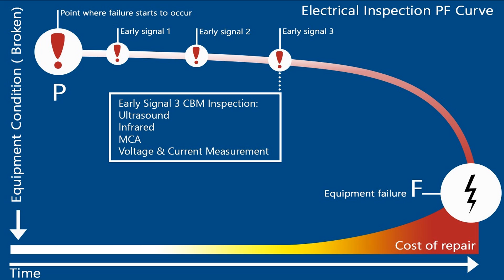We will see thermal patterns expanding rapidly, again outside of the acceptable alarm levels, and you may come across the third phenomenon that we can find with ultrasound, which is arcing. And arcing sounds like this.